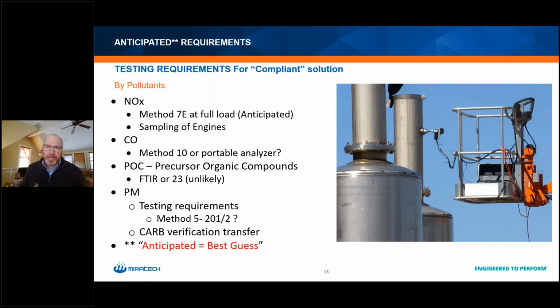So here's what we think the additional requirements associated with this will be. Again, you put in your diesels, you're putting in after treatment - what are the testing requirements going to be if you're going to do this compliant path? We know they're going to ask for a NOx test - there's no way they're not going to ask for some sort of NOx test. What we believe it's going to be is EPA Method 7E.